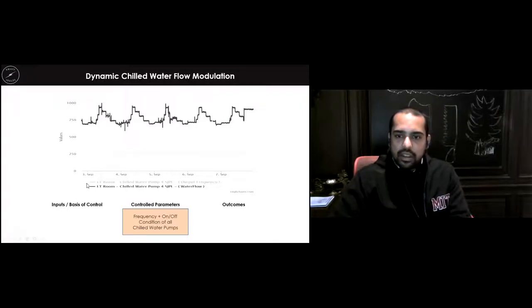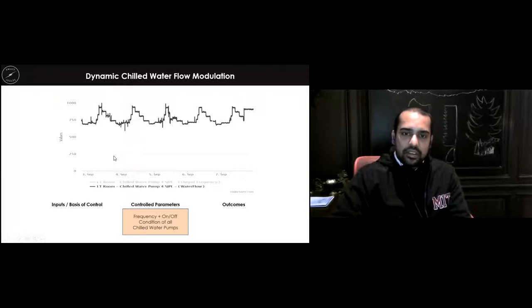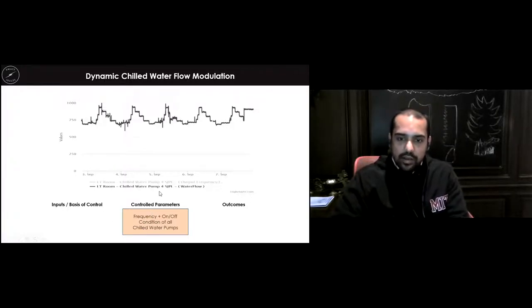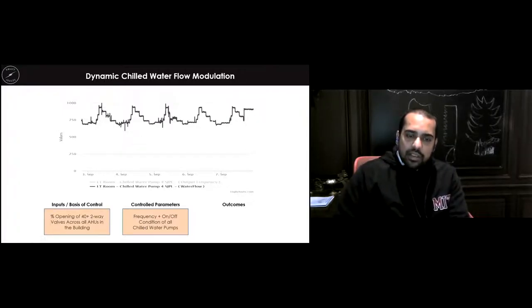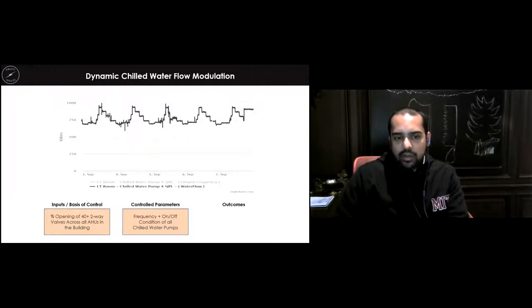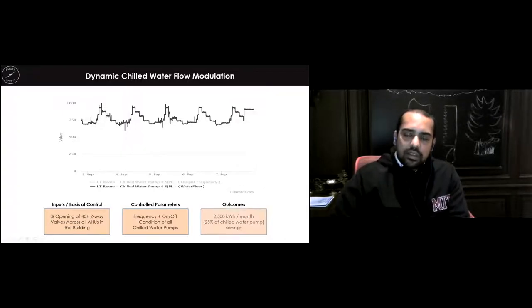So you can see in this graph, over multiple days, what is the pattern of the flow? There is a certain pattern, but it's not exactly the same every day because it depends on a number of inputs. So, the Joule recipe concept is controlling frequency and on-off timings based on the air conditioning requirements in the building. Very specifically, it's looking at, out of the 40 plus two-way valves in the air handling units of the building, how open are they? These two-way valves are controlled based on the temperature requirements and actual conditions. So, if all the two-way valves are open, then the flow would be very high. If some of them are closed, let's say an area is not occupied, then the frequency will be low. So it's automatic control of chilled water flow based on the requirements of the particular system. And this saves a lot of energy. About 25% of the chilled water pump's energy is saved just by dynamic modulation of the frequency of pumps.